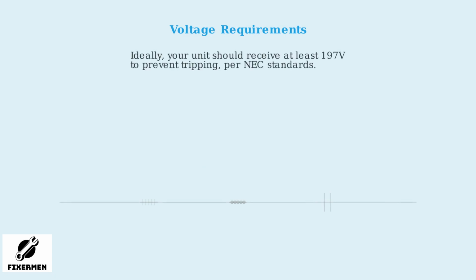Ideally, your unit should receive at least 197 volts to prevent tripping, as required by National Electrical Code standards. Voltage drops caused by weak wiring or other appliances running simultaneously exacerbate the problem. We will explain how Ohm's law affects this. According to Ohm's law, voltage equals current times resistance. When resistance is high due to weak wiring, even normal current can cause voltage drops that prevent the motor from reaching the required 197 volts.